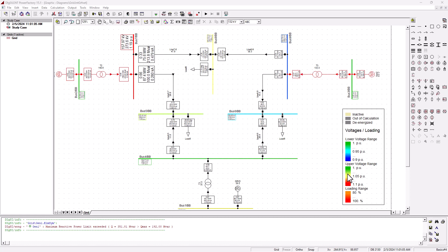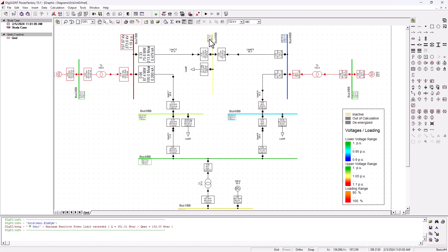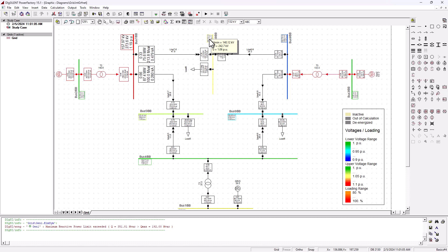After executing our calculations, we can see that the bus voltages are all not the same. We got a nice spectrum here to exactly display it to us. We also have the upper voltage range that is from one per unit to one point one per unit. When we look at the center of the screen here, bus bar eight is yellow, which means it falls under this spectrum.